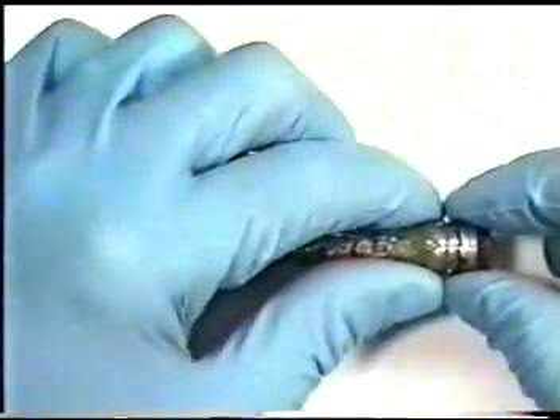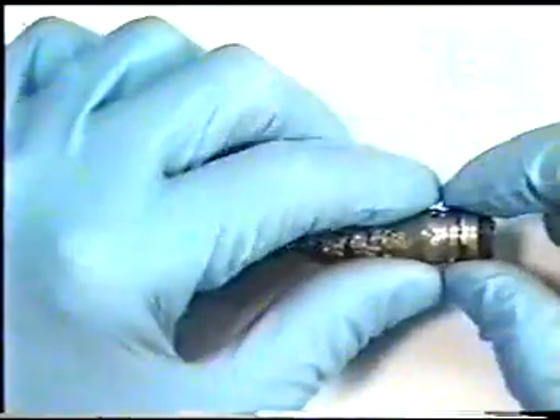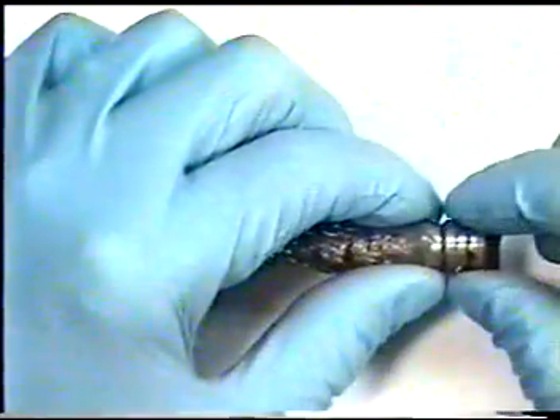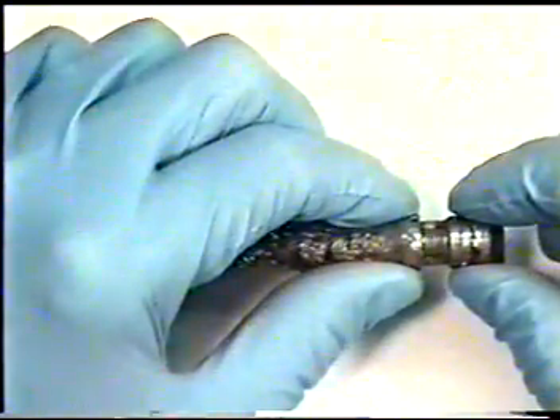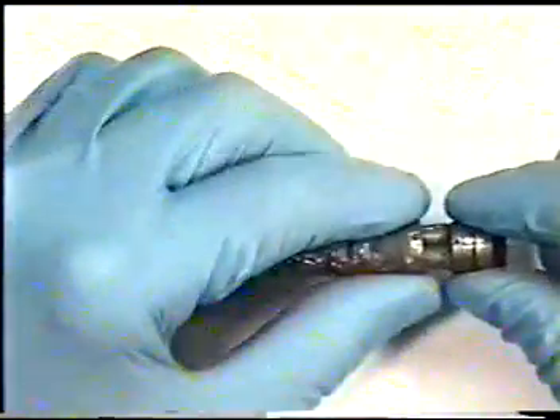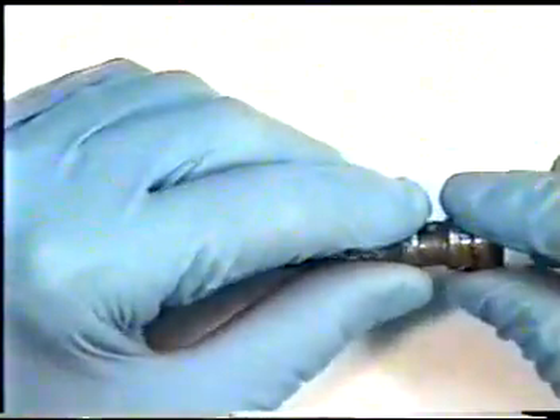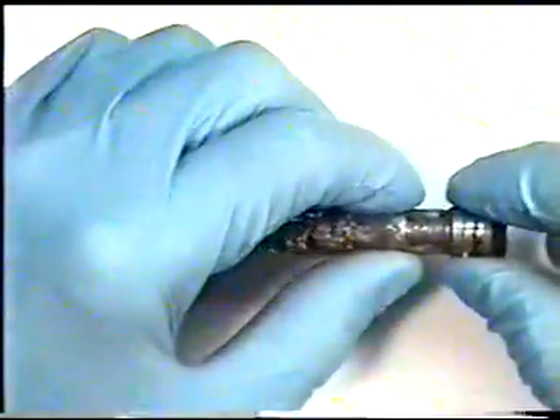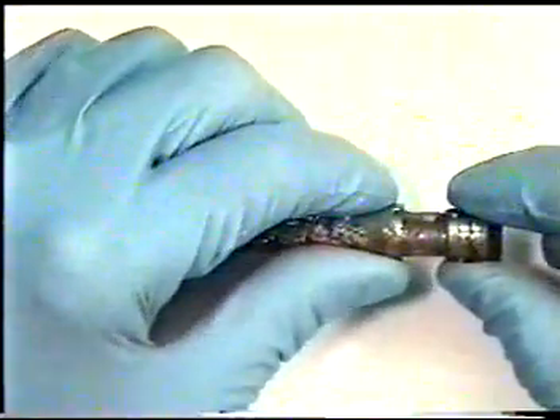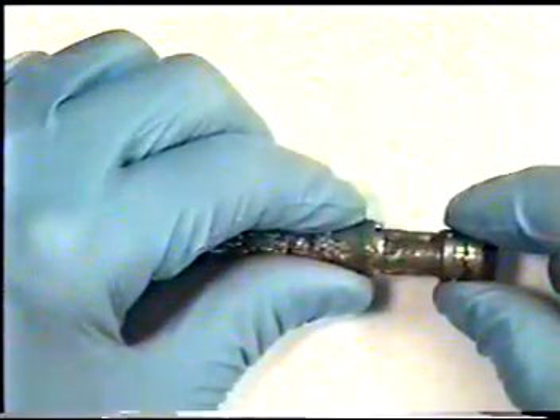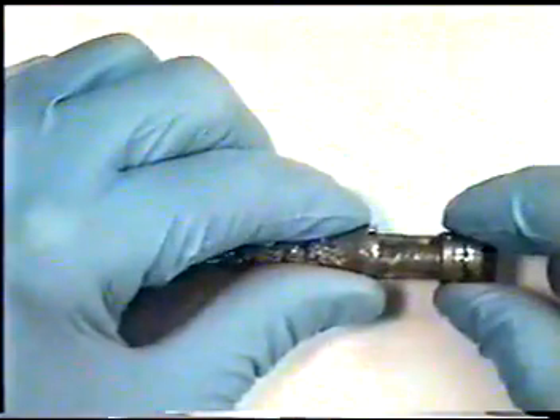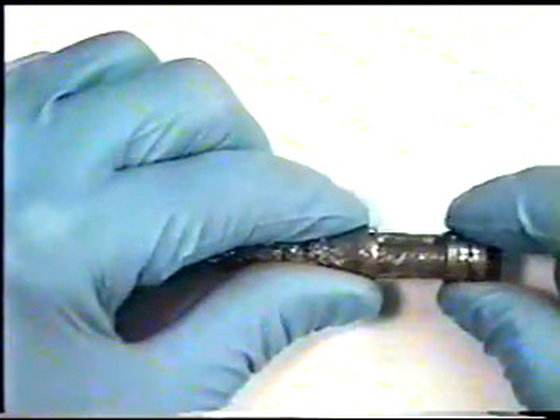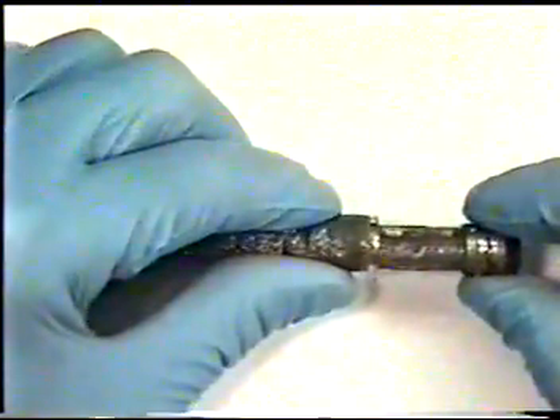Once both screws are removed, carefully slide down the bending section from the distal end. Be careful not to pinch or cut any of the air-water channels, CCD or image guide bundle. Slide down bending section approximately 1 inch.